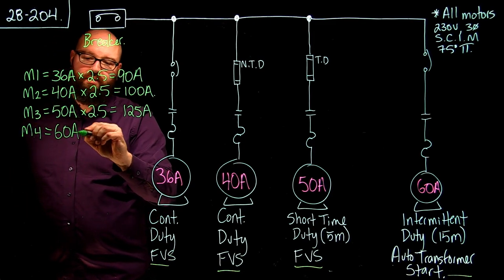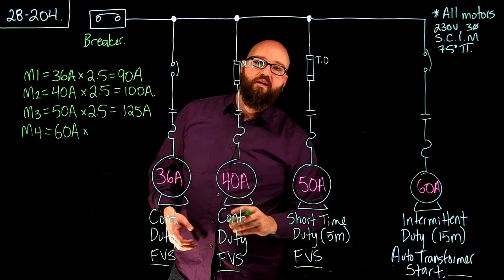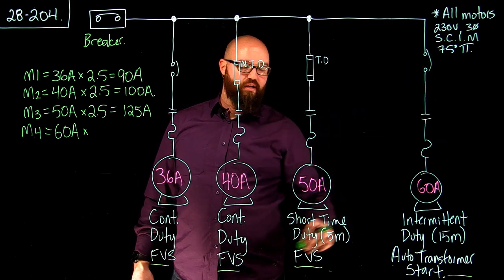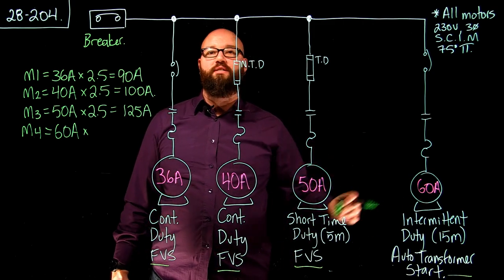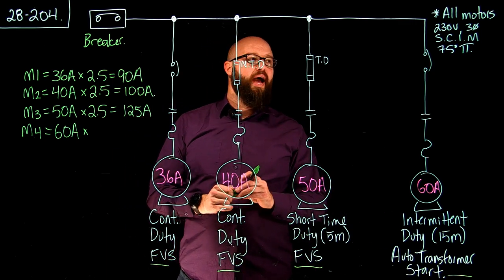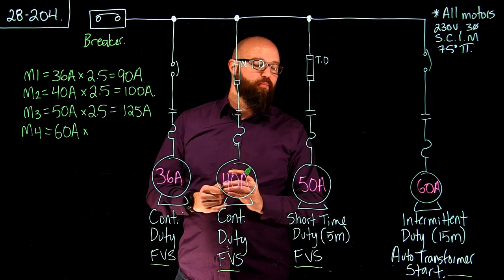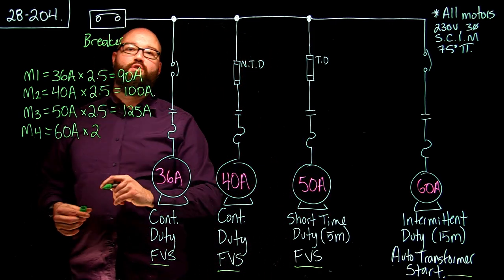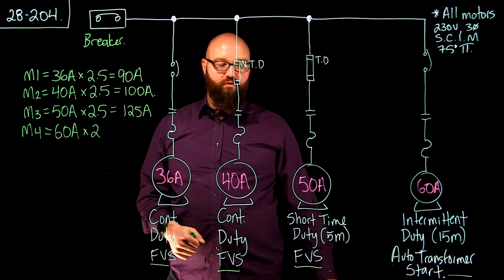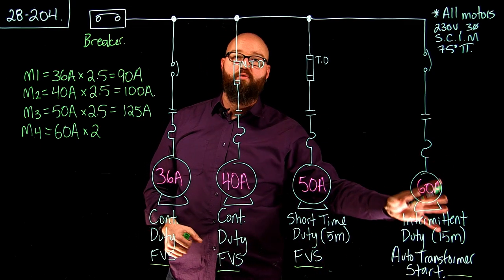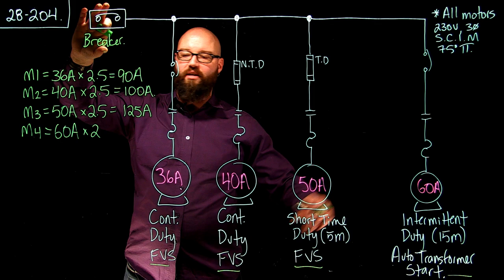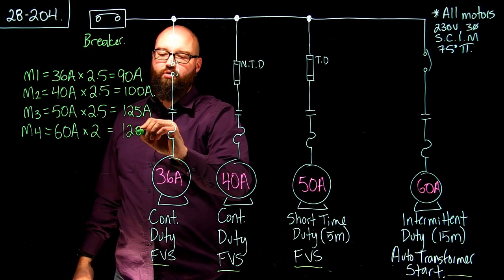Motor 4 has an FLA of 60 amps. When we go to Table 29, we look for our squirrel cage induction motor, but it's no longer a full voltage start — we have an auto-transformer start. We go down that column until we find the auto-transformer start entry, and we find that for over 30 amps, we have a multiplier of 200%. So for a breaker with an auto-transformer start, our multiplier is 200%, and 60 amps times 2.0 gives us 120 amps.